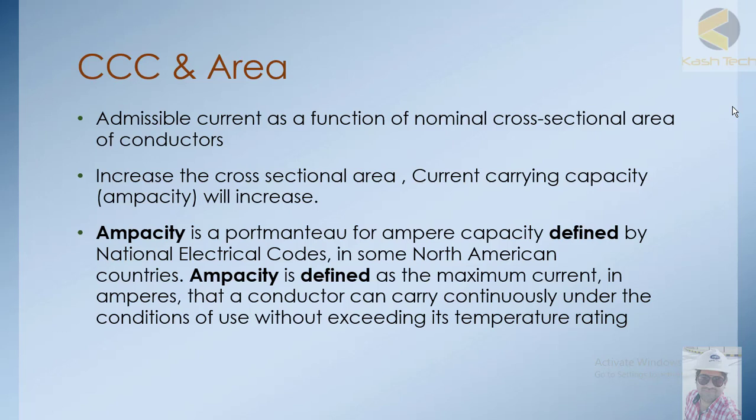In this session we will discuss cross-section area and current carrying capacity — basically admissible current as a function of nominal cross-section area of a conductor. As a thumb rule, if the conductor cross-section area is increasing, the resistance of the conductor is decreasing, there will be less losses, less heat effect, and the current carrying capacity — called ampacity — will increase.